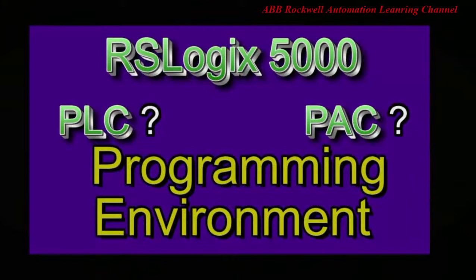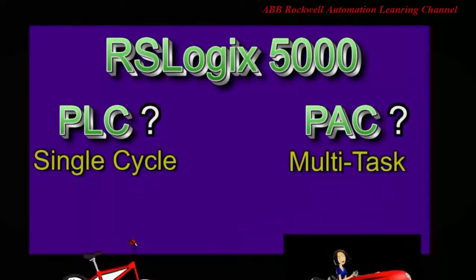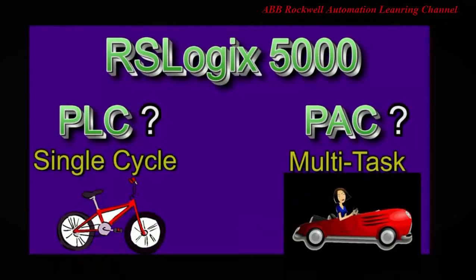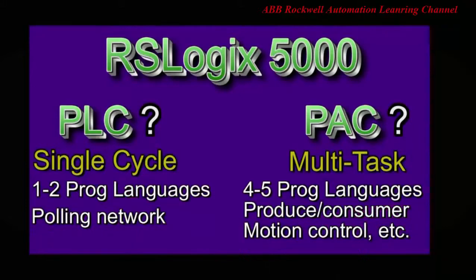A PLC runs a single task, scan cycle, in a loop, like a wheel on a bicycle. A PAC is like a car in comparison, allowing multitasking and multiple functionalities. A PAC can take the place of multiple PLCs. A PLC typically has 1 to 2 programming languages. A PAC, 4 to 5.